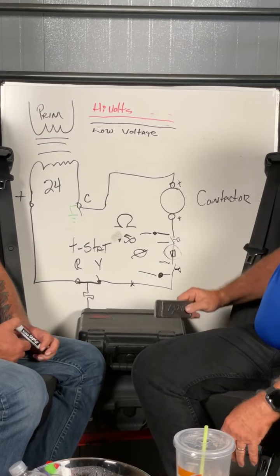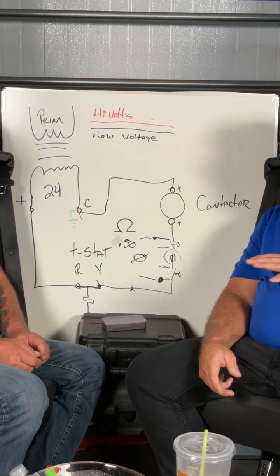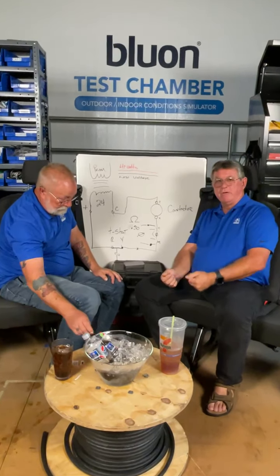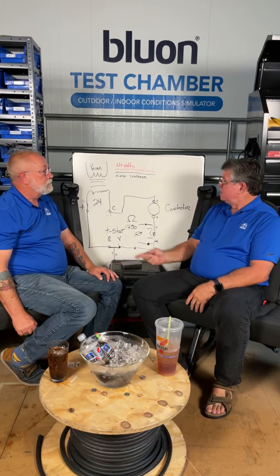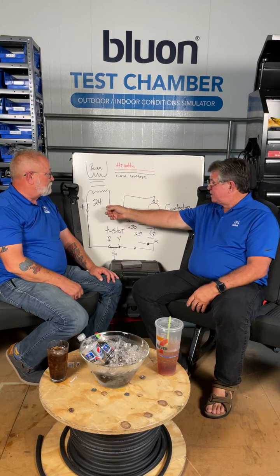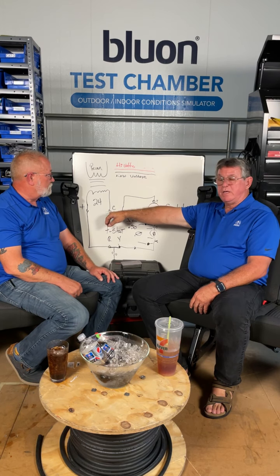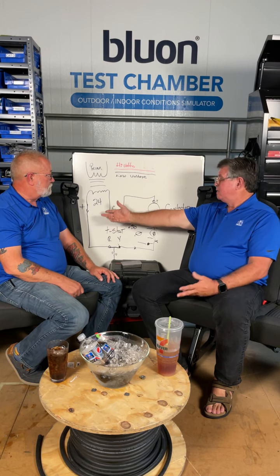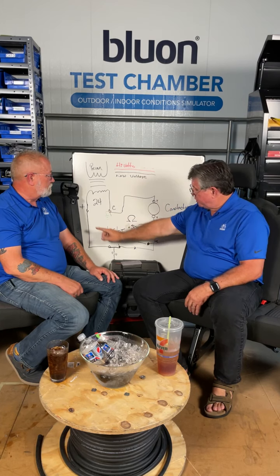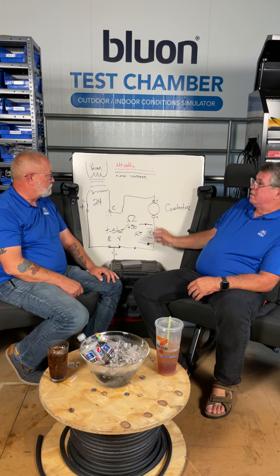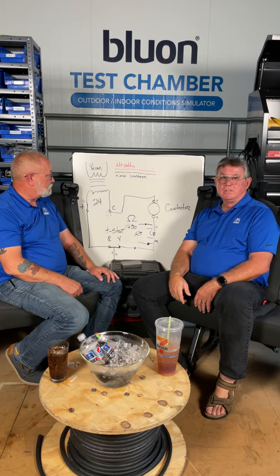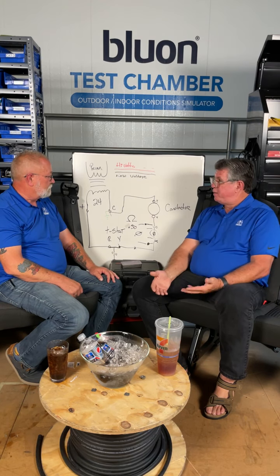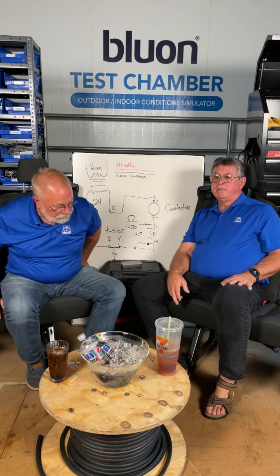So there are gonna be things that you can't see unless the equipment's powered up. And if you're powering it down and trying to read continuity, it doesn't always work. So another way to do it is just to put your alligator clamp from your common leg on here and put it on your appropriate voltage and just go boom, boom, boom, boom. Oh, I lost it there. And it'll get you to where you're going without having to power down the unit. So there's some different ways of doing it.